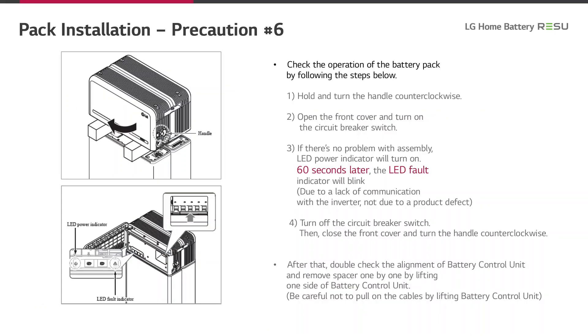The next steps are necessary to check whether the battery control unit is properly connected to the battery modules. First, hold and turn the handle counterclockwise. Open the front cover and turn on the circuit breaker switch. If there is no problem with assembly, the LED power indicator will turn on. 60 seconds later, the LED fault indicator will blink — this will happen due to a lack of communication with the inverter, not due to a product defect. Then turn off the circuit breaker switch, close the front cover, and turn the handle counterclockwise. After that, double check the alignment of the battery control unit and remove the spacers one by one by lifting one side of the battery control unit. Be careful not to pull on the cables when lifting the battery control unit.